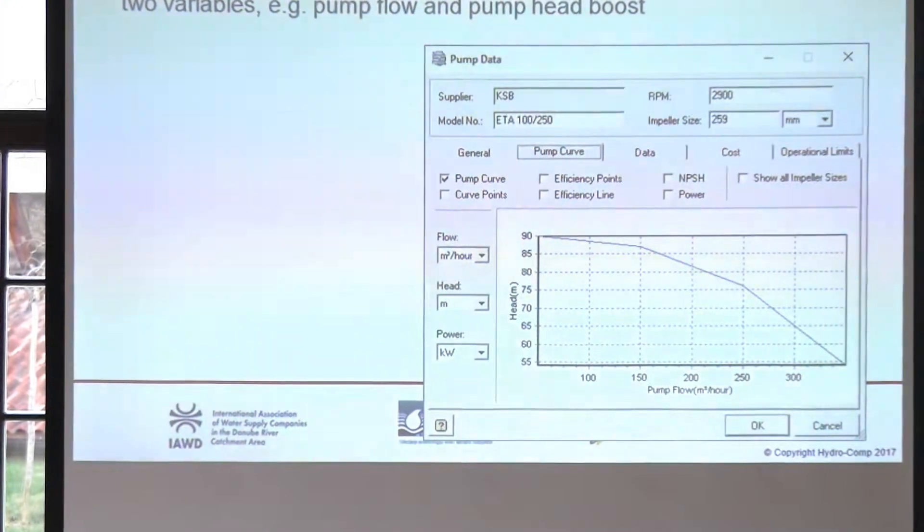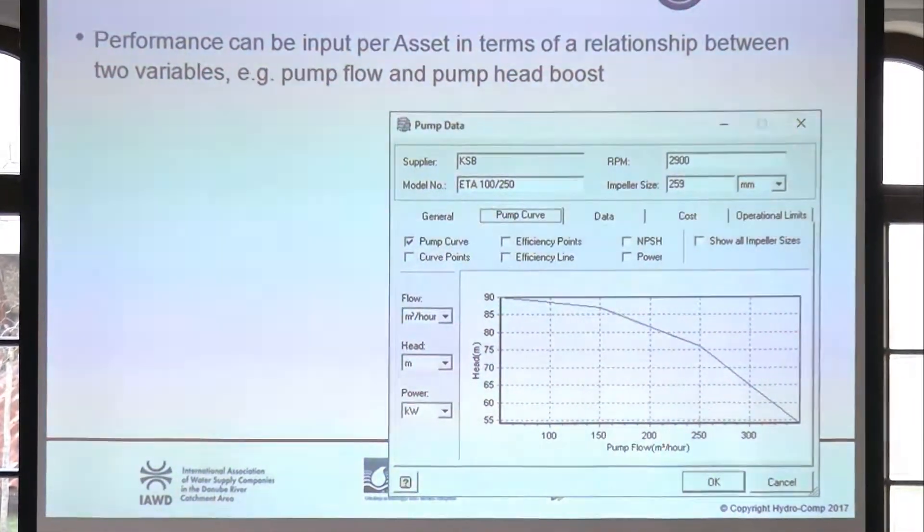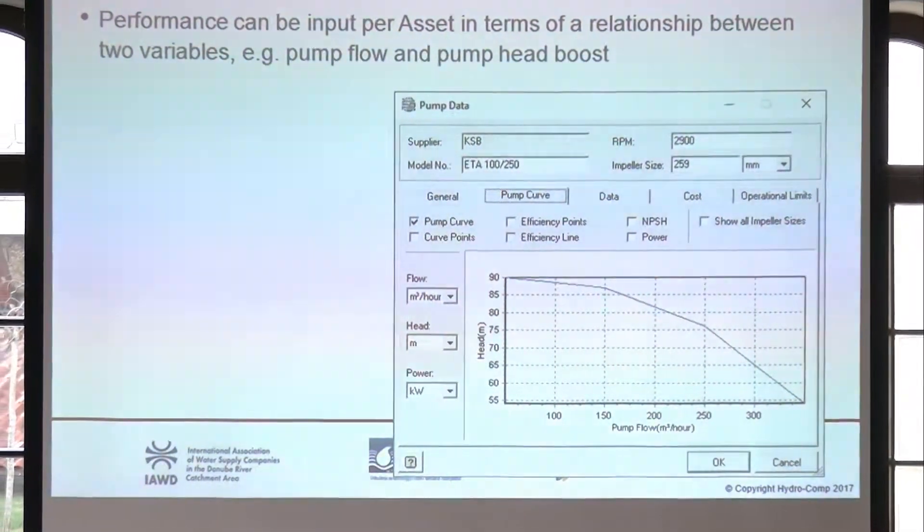This is critical information — it's straight money. We can also easily calculate how much it's costing you to produce each cubic meter — your cost of sales. And we can take it a final step: the system, using a new feature we developed, will automatically tell you how your pumps are doing. For every single pump, if I have the duty flow and your numbers — what you're pumping at what head — I can tell you if the pump operates efficiently or inefficiently, how much it's costing you, and how much money you're losing because of pump inefficiency.